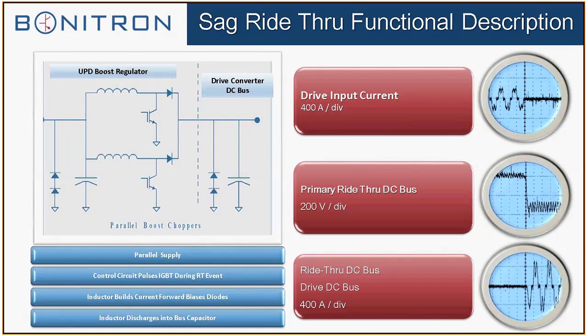So the way the ride-through functions is it watches the DC bus, it monitors the DC bus threshold, and when it gets to the potentiometer-settable DC bus threshold, which we set in the factory, we don't recommend adjusting the DC bus threshold in the field. We test them and we set them up for the exact voltage that the customer requires. So there shouldn't be any kind of adjustments, any kind of jumper settings or anything like that that you have to mess with once you get the ride-through on site and they're getting ready to install it.